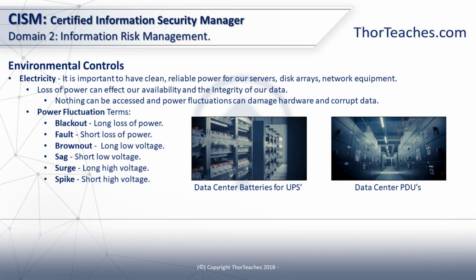We touched briefly on clean power earlier, but it is important to have clean, constant power and constant voltage. If we don't have that, we obviously can compromise the availability of our servers and our environments, but it can also compromise the integrity. If we have no power, our system's obviously down, but if we have no surge protectors on our system, a high voltage can damage the hardware or corrupt the data too. We use the UPSs for that and the PDUs.